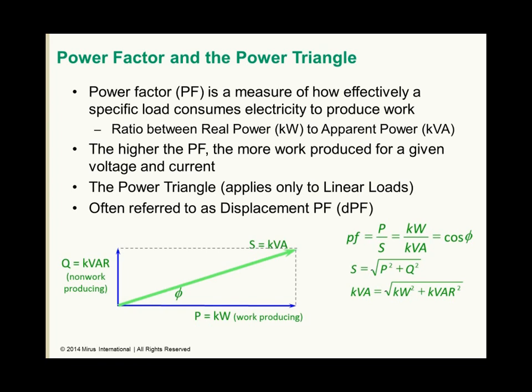The power triangle shown on this slide, though, applies only to linear loads. It shows the reactive power component in kVAR, inductive or capacitive, upwards being inductive, downwards being capacitive, and the real work component in kilowatts on the x-axis. The vector sum of these two powers results in the apparent power, or kVA. Power factor, being real power over apparent power, is equal to the cosine of theta. Also, apparent power can be represented as the square root of the real power squared plus the reactive power squared.